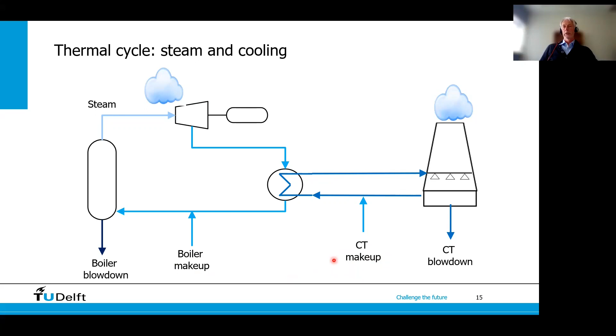So in this scheme we see two waste streams of different quality. They can be mixed and treated, but can also be reused. And there are two makeup streams, also of different quality. For a boiler we need high quality, ultra pure water, especially for high pressure steam. The makeup water for the cooling tower is a bit less critical, but still needs to be good quality.